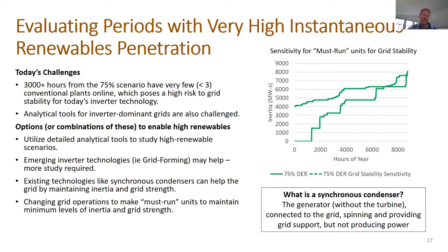And as I had mentioned, the simulation and analytical tools for operating grids with such an inverter-dominant operation or characteristic are also challenged. But that's not to say that it cannot be done and cannot be analyzed. For this, we were using the PSS/E software, which is the same software that PREPA uses and many operators across North America use, but there are some known limitations when you get into these very high instantaneous renewable penetrations. And there is another set of tools that have higher fidelity models of the system that are designed and intended for looking at these particular cases.